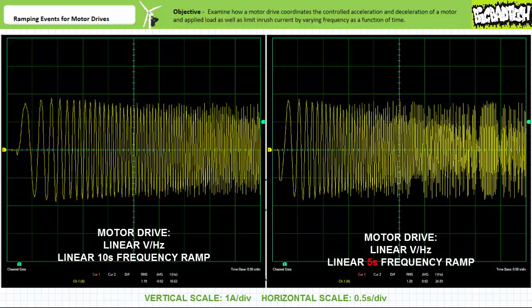For the purposes of comparison, a graph of line current for a motor drive using a linear volts per hertz ratio and a linear 10-second ramp-up time appears next to one employing a linear volts per hertz ratio and a snappier linear five-second ramp-up time. Note that both plots illustrate linearly increasing applied voltage and excitation frequency; only the one with a shorter acceleration time does so more rapidly.